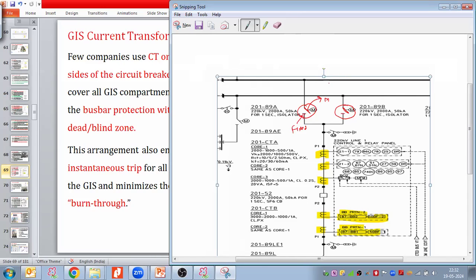This is not the GIS manufacturer SLD. This SLD is prepared by the EPC company design engineer. This kind of representation comes here. I recommend to all of you, when you prepare the SLD, do not represent the disconnector like this. Just make it reverse, meaning take the fixed contact towards the bus side and the moving contact towards the breaker side.